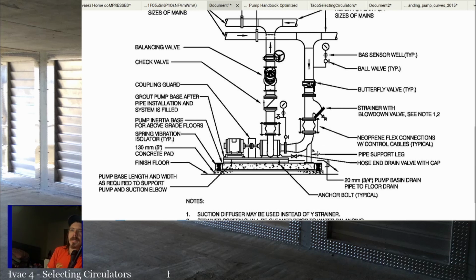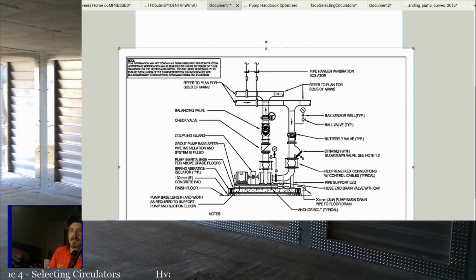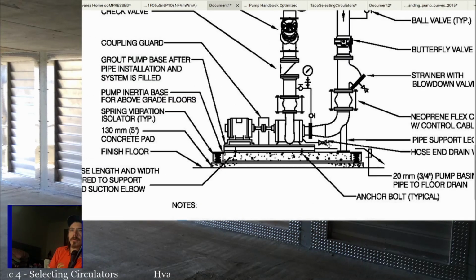Now when we get to here, if you're talking about an end suction pump, it looks like this. All right. An end suction pump is one where it's mounted horizontally. You're going into your suction on the bottom horizontally here, and then it pumps up out vertical. If you're doing an end suction pump, you get a 90 over into the suction side a lot. If you're doing an inline pump, this is going to go straight through.